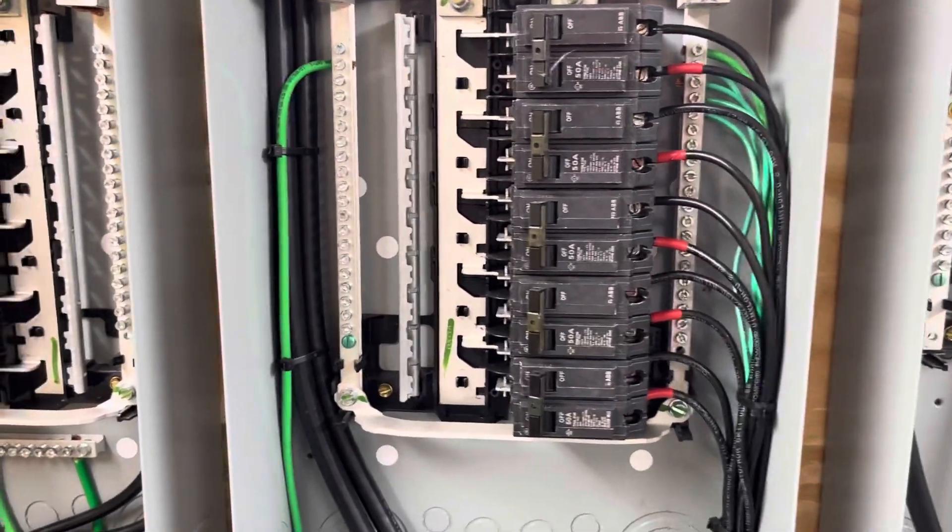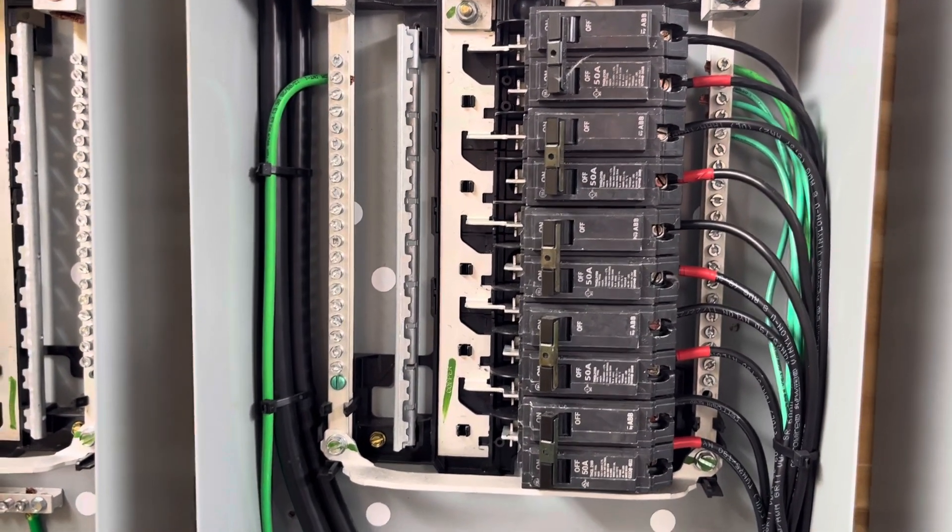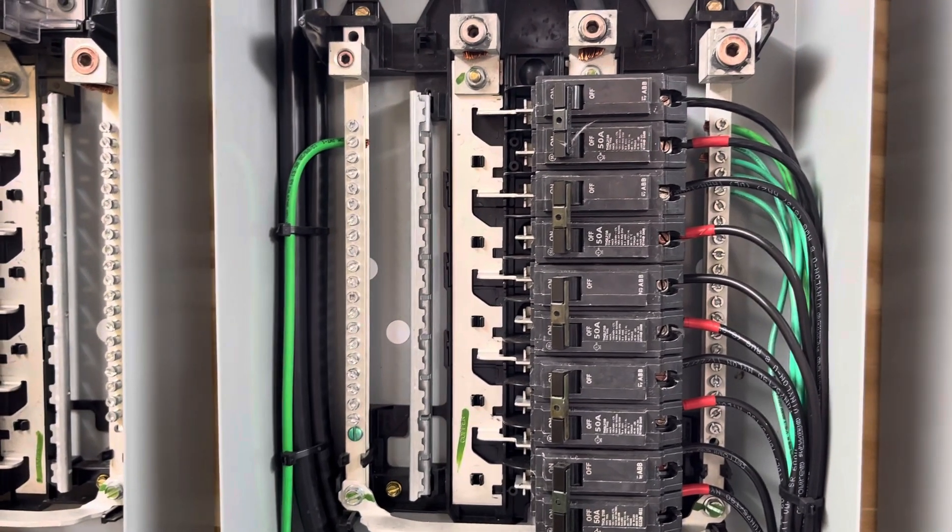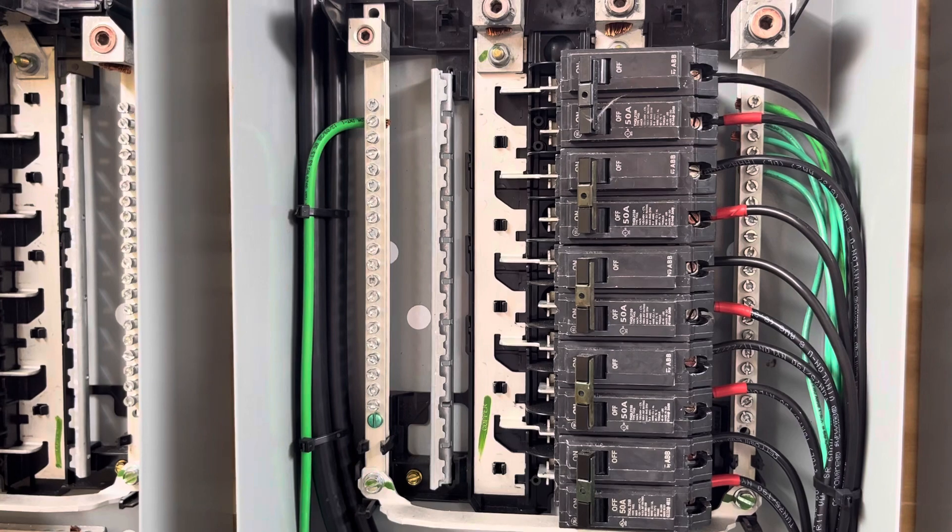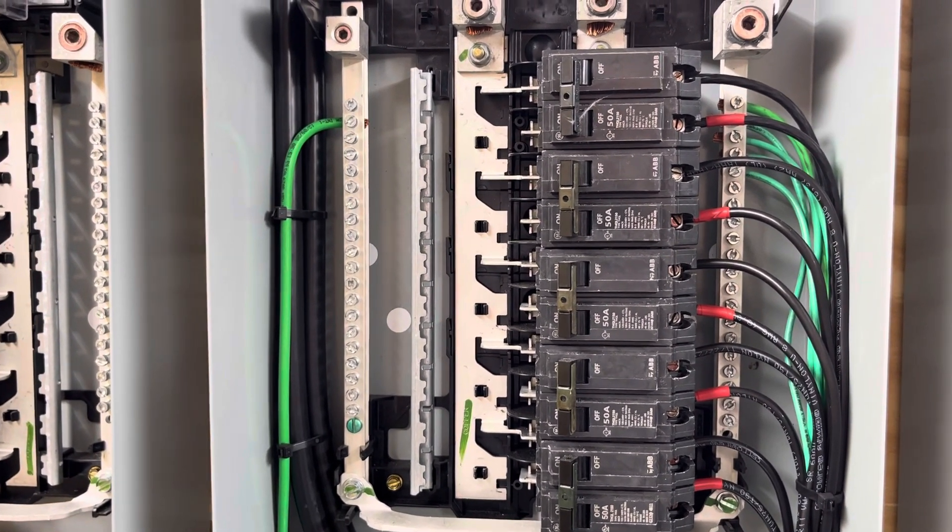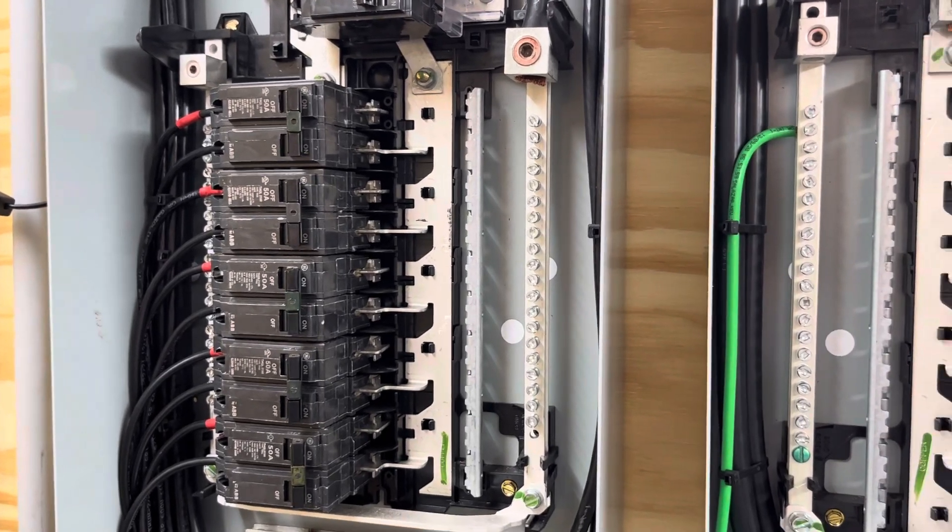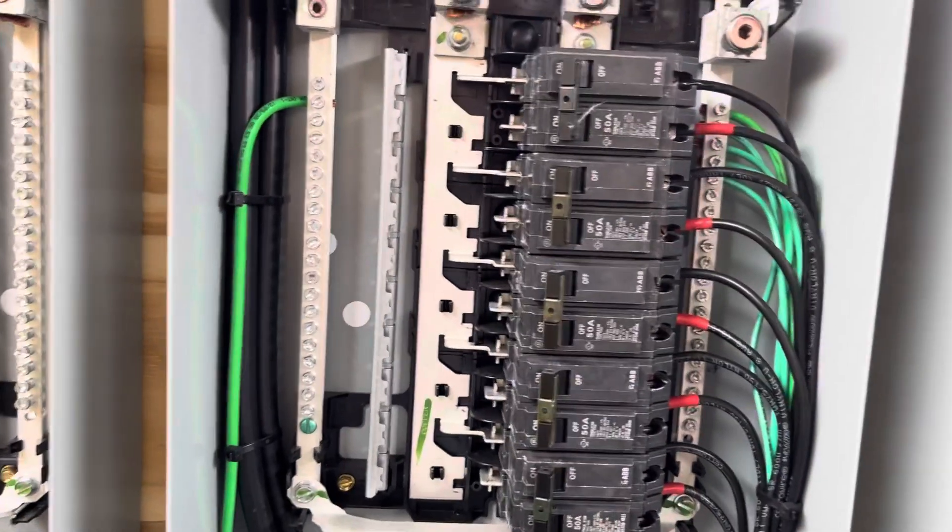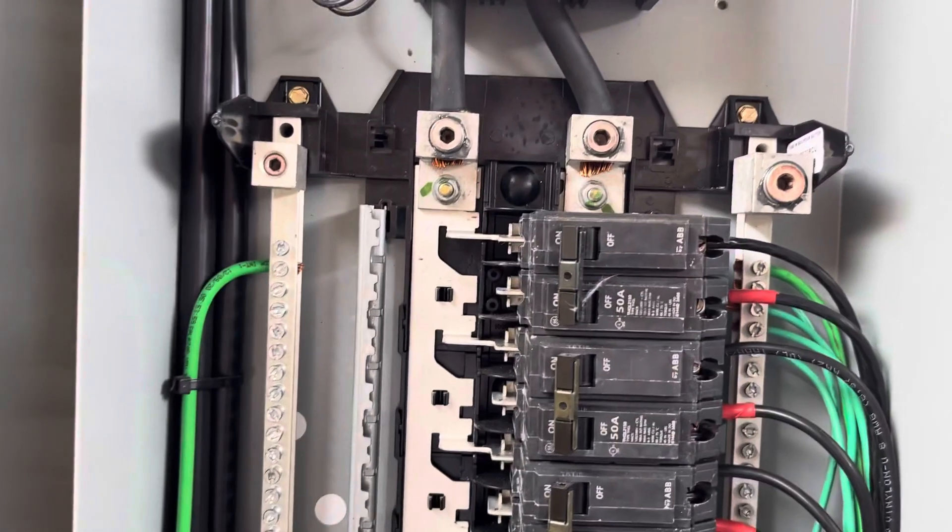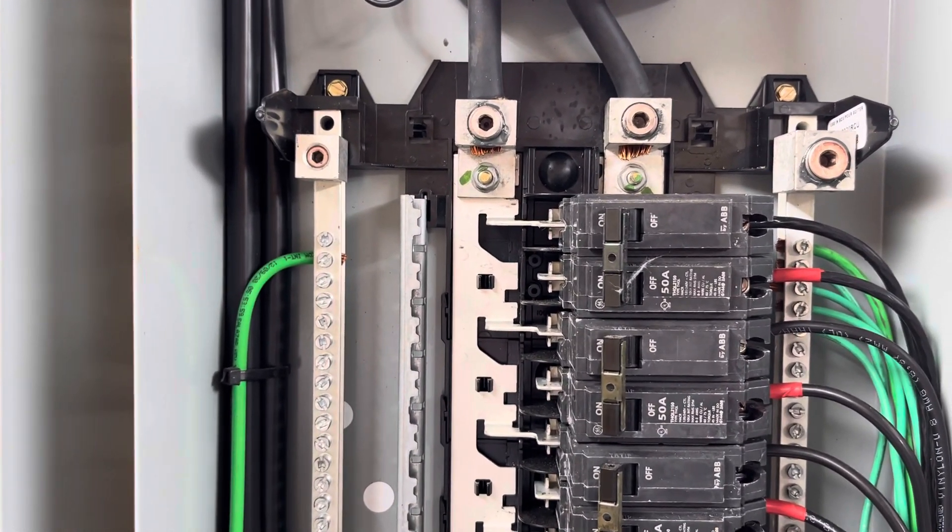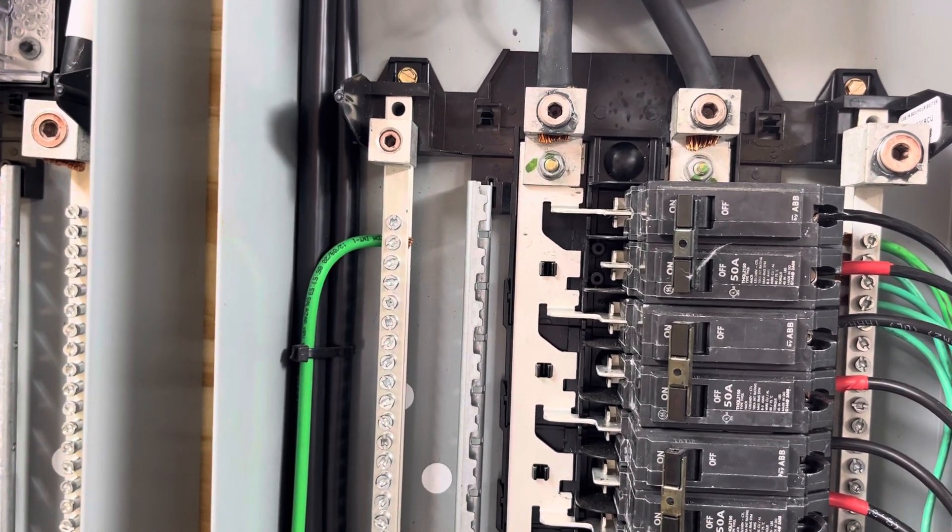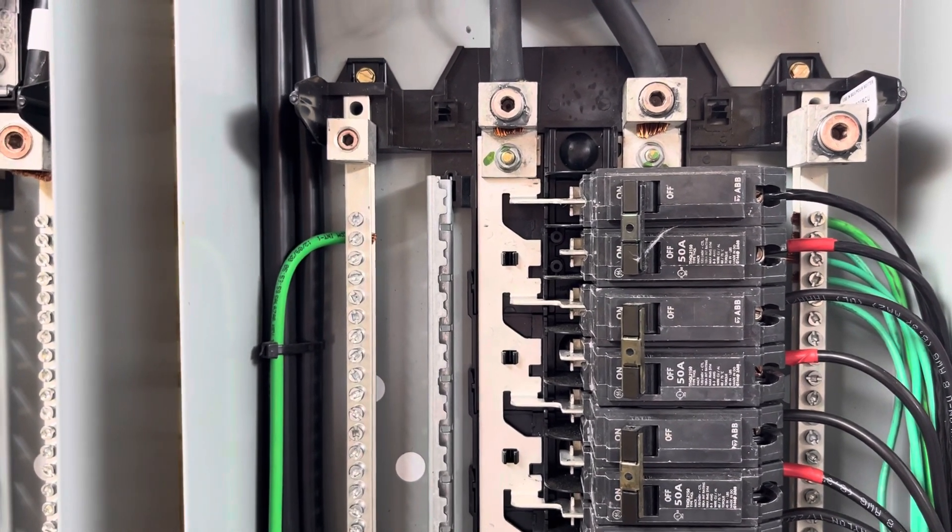Now, as I've shown in a previous video, the voltages referenced to ground changes on the output of that inverter based upon whether it's in bypass mode or inverter mode. When it's in bypass mode, the grid power passes straight through the inverter and comes straight here. And in that case, my voltage from line to ground is 125 volts. It's got a reference because the grid is coming straight through, and the grid ground is tied to the neutral. So I have a ground reference, and I can check the voltage.